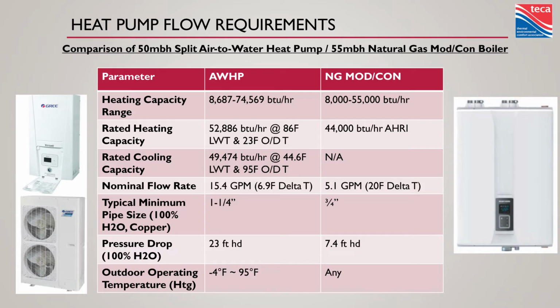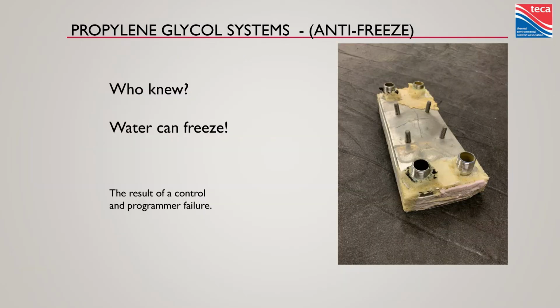And at 131, we have lost a lot of capacity and a lot of efficiency. So don't design for those maximums. Be aware of the maximums. Design even lower, because if that's a monoblock, that's 131 leaving the unit outside on a cold day. Are you getting 131 into your floor? Probably not. And that's at its least efficient. Glycol, I already kind of talked about this stuff, so I'll skim over that. But turns out water freezes without it.